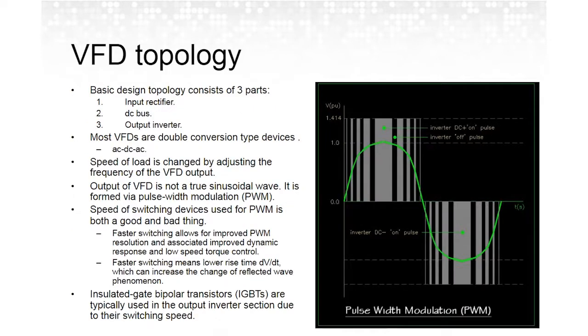Moving on to the next slide. VFD topology. Again, VFDs are power conversion devices. Typically, most of them that you will see are double conversion devices consisting of 3 parts. You have an input rectifier, which takes your incoming AC power and converts it to DC power. You have a DC bus where that DC power lives, and then you have the output inverter, which takes the DC voltage from that DC bus and resynthesizes an AC waveform.